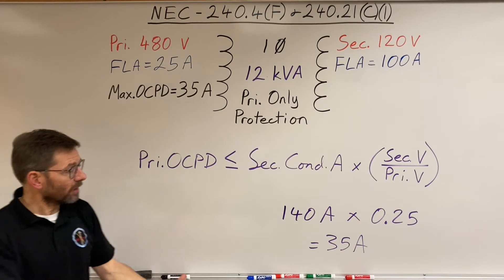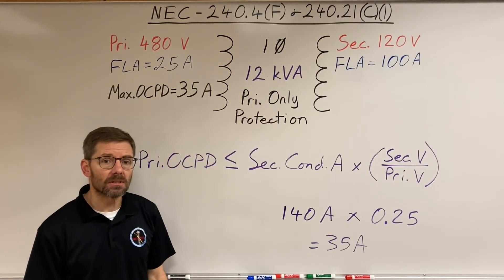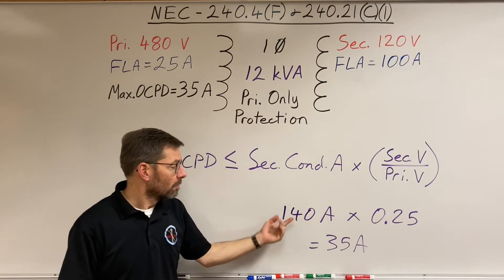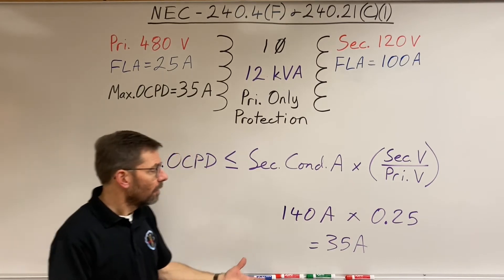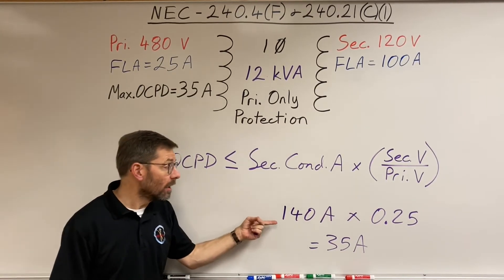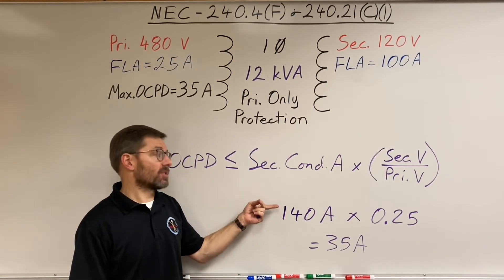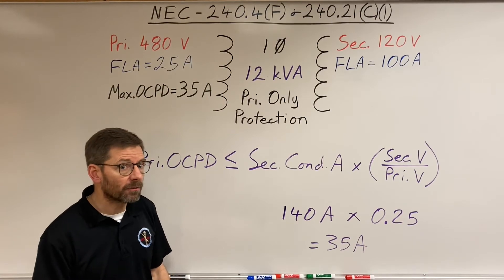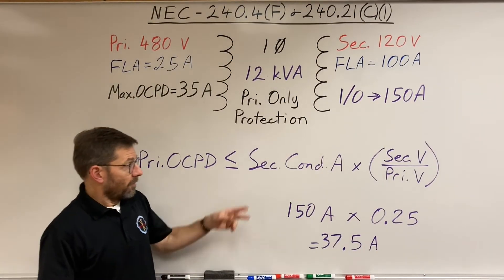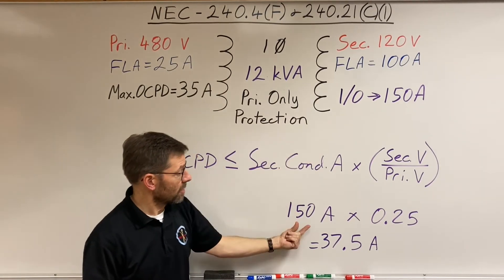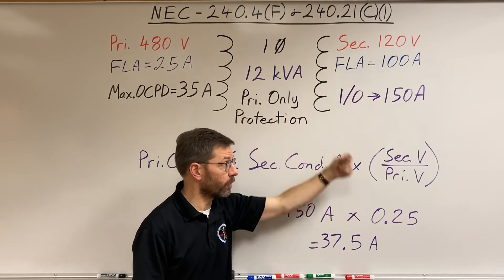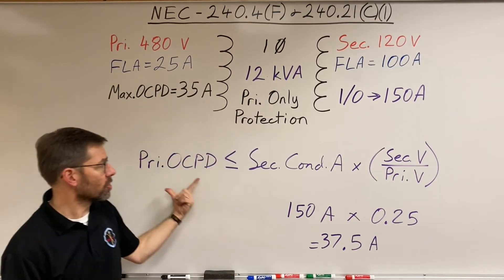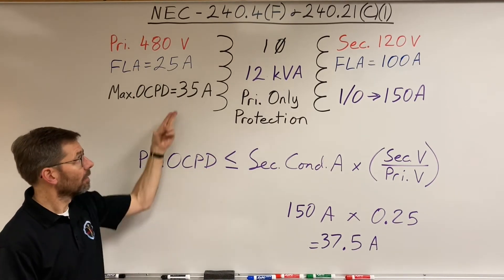So what conductor do I have that could meet 140 amps? Let's look at our ampacity table 310.16. I don't have a conductor that hits 140 amps. A number one would be 130 amps, or a one-aught would be 150 amps. So in this case, I'd have to go with a one-aught for 150 amps. And if I plug it into the formula, 150 amps times a quarter would require no bigger than a 37 and a half amp circuit breaker. The breaker would need to be less than or equal to 37.5 amps. And a 35 would work.